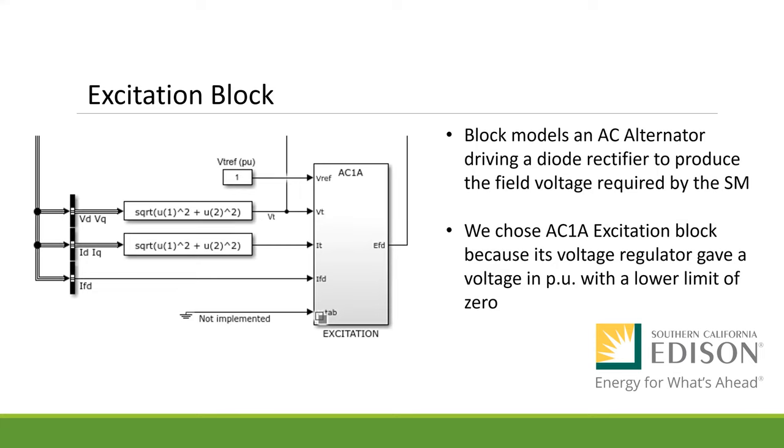The excitation block models an AC alternator driving a diode rectifier to produce the field voltage required by the synchronous machine. We had options such as AC1A, AC4A, AC5A, and DC1A. We chose to use AC1A because its voltage regulator gave a voltage in per unit with a lower limit of zero. This was a great fit to our model because most of our values were in per unit.